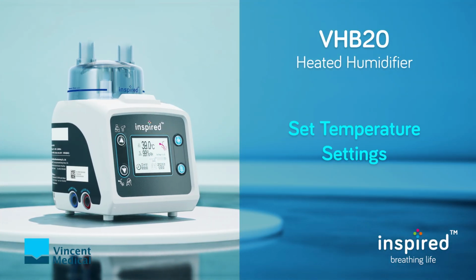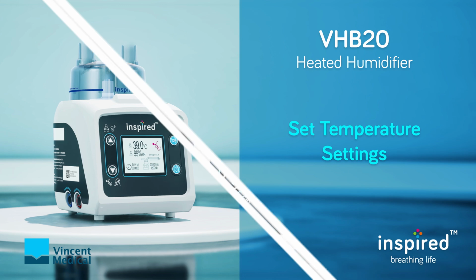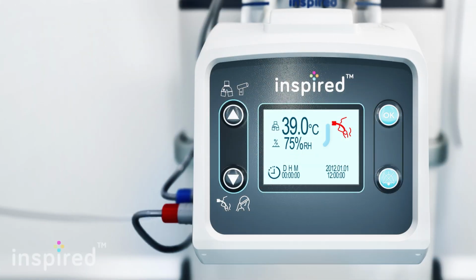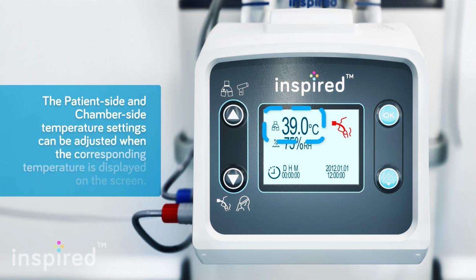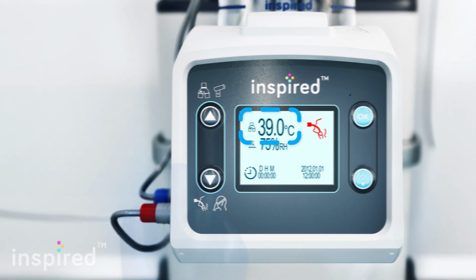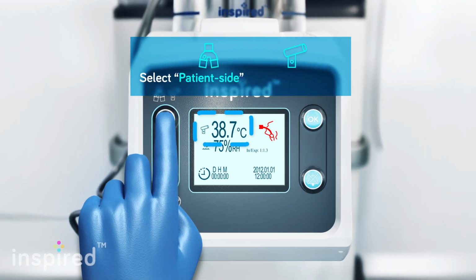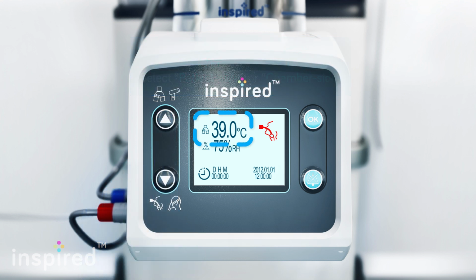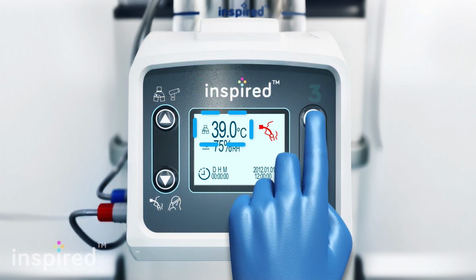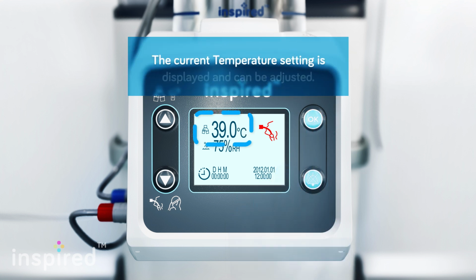Set temperature settings. The patient side and chamber side temperature settings can be adjusted when the corresponding temperature is displayed on the screen. Select patient side or chamber side. Press and hold the OK button for 3 seconds. When the temperature symbol degrees Celsius is flashing on the display, the current temperature setting is displayed and can be adjusted.